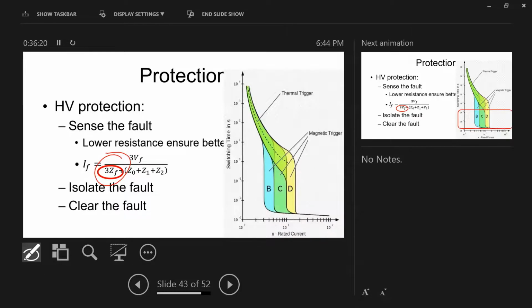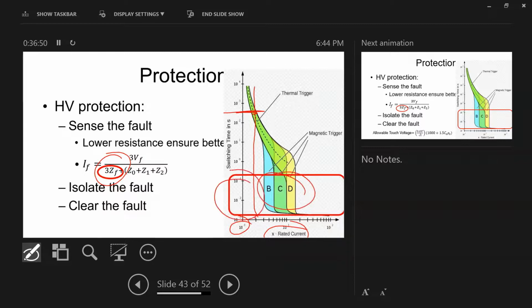And look, guys, the circuit breaker. The bigger the current, the faster it trips. Look, if the current is exactly the same, this is the same 10 times the rated current, it will not trip here. If it's in here, if it's 10 to the 1, if you multiply it by 10, I need it to trip in this location. I needed to trip in 100 milliseconds, 200 milliseconds, 80 milliseconds. I wanted to trip very fast.